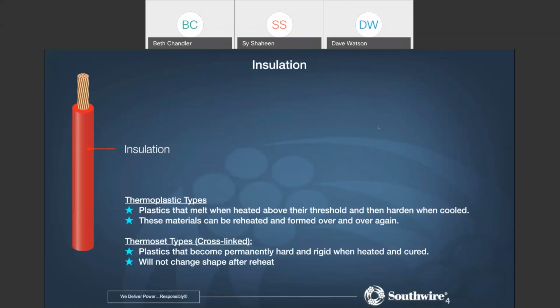So we're going to get right into talking about the insulation and the way this kind of differentiates our single conductor products. So the insulation over the copper or aluminum bare conductor, we break it down into 2 basic types. And this is really based upon how they perform and how we manufacture those. So these are the thermoplastic and thermoset types of products. Now the thermoplastics, these are plastics that melt when they're heated above their threshold and then they harden when cooled. So PVC is the most common one that you'll encounter in wiring cable products. So these materials can be reheated and formed over and over again.